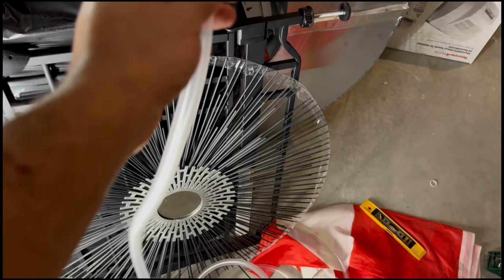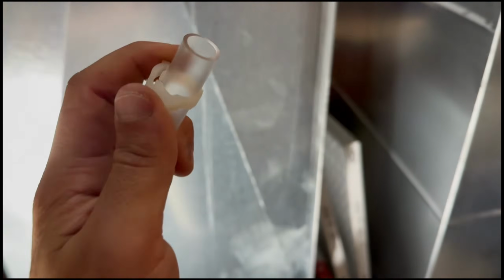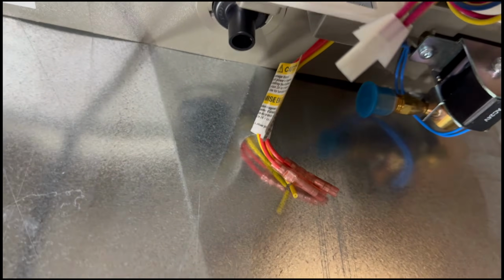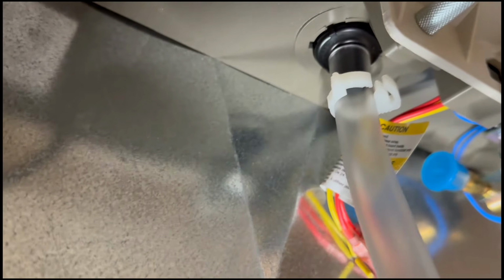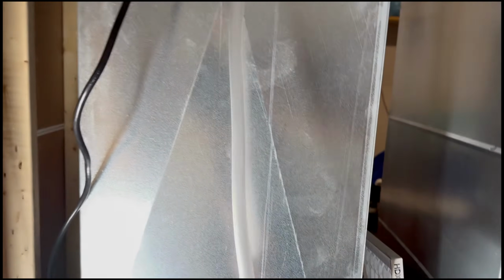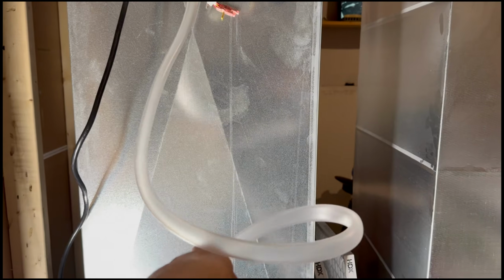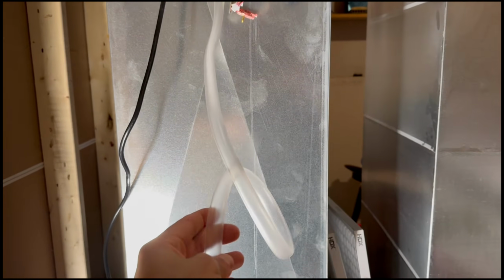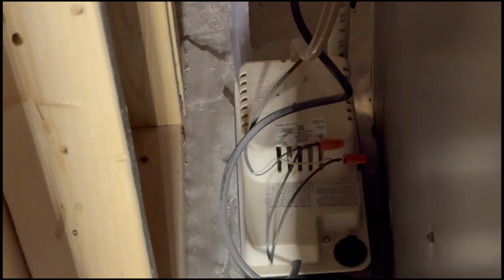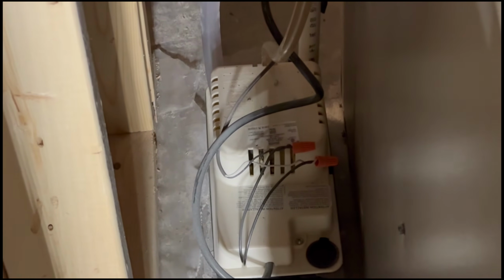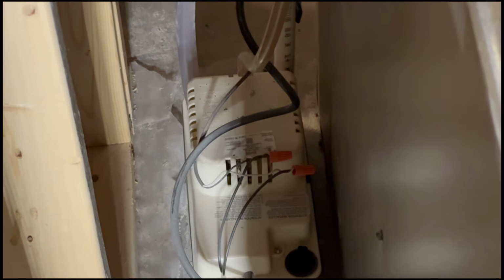First thing we need to do is connect our drain hose. So this is the drain hose and it's got a little clamp at the bottom. You're going to install that. At the bottom of the unit, there is a nipple, which you'll make sure it's securely fastened all the way up. And then you're going to take that clip and clip it in. Once it's clipped, then you need to run this drain hose to a drain. You either have a drain in the ground or you have a separate unit, which I do right there, that connects all of your drains and then pumps it out into the one single drain located in an alternate location.